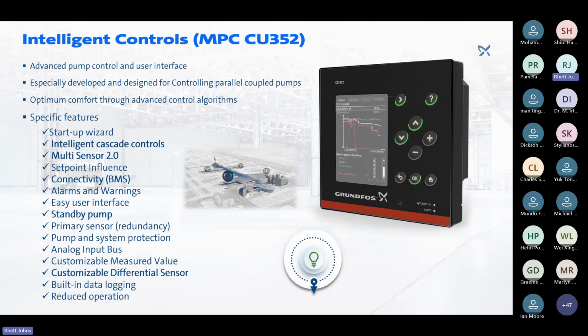Using a system like this in the pump controller, you get benefits such as built-in control systems. So you can have things like pressure control, proportional pressure control, temperature control, proportional temperature control, level control, multiple different control scenarios that are built into the system, and you're not necessarily reliant on a controls programming team that would have to write this code from scratch. And using a system like this, you can run the pumps at the optimal efficiency point.